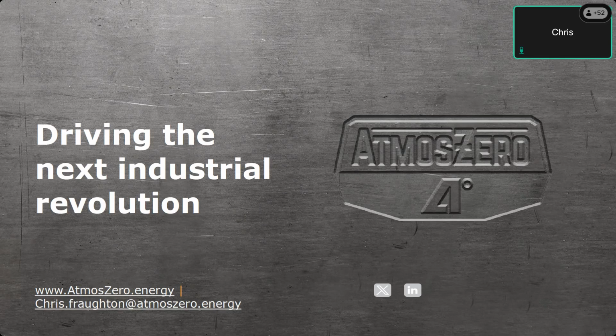And then below 50%, you really need to turn the units off because the compressors are starting to run and choke, and you could potentially damage the compressors. And so our control system takes care of all of that. You don't have to worry about it, but it is something that we're going to set up and talk to you about during the commissioning process.